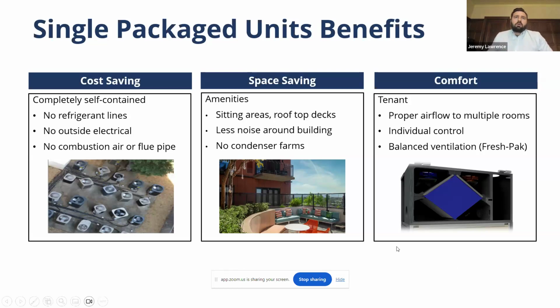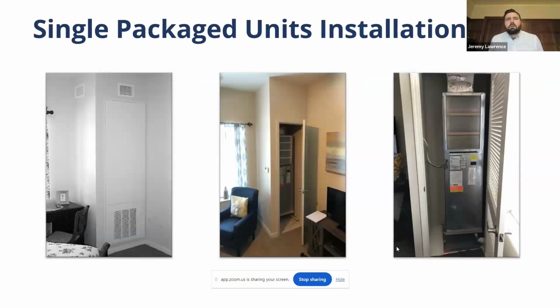And of course, comfort, having the built-in ERV, having that fresh air coming in anytime the unit is running is always a benefit. We need to be putting ERVs into our systems anyways, and this is an excellent way of doing it while it's all wrapped into one space or one unit. So this common install of the PTACs, they fit in very sleek and small space closets. This access panel here acts as both access for service and the return air, and these panels are manufactured for these units by First Company, but most commonly a standard closet door is used in installs.